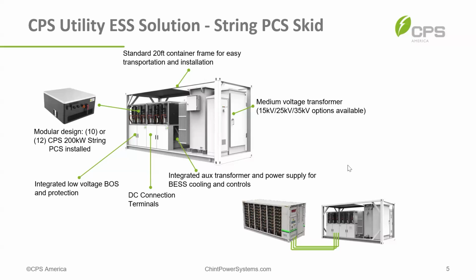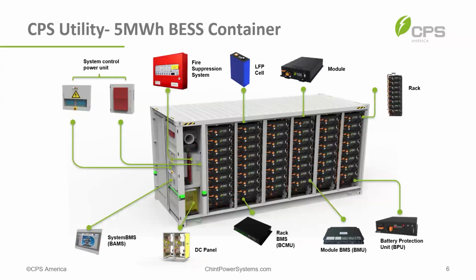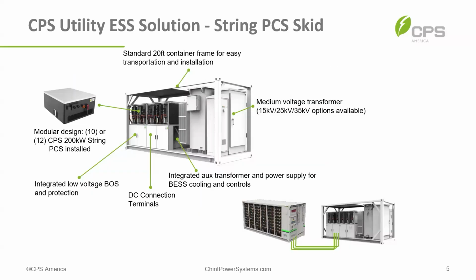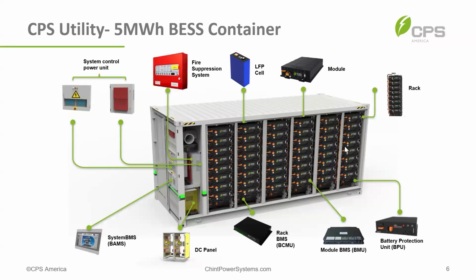And just like microinverters are easy to swap out, we've made these easy to swap too. If one goes out, you go up to it, turn off the disconnects for that PCS, unplug about 3 cables on the back, 2 on the front, plus a comms cable, slide the whole thing out, and slide a new one in. You can do it in about 30 minutes to an hour.